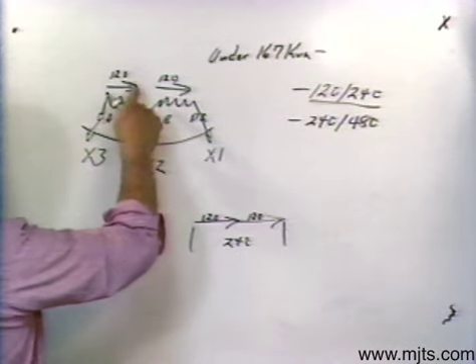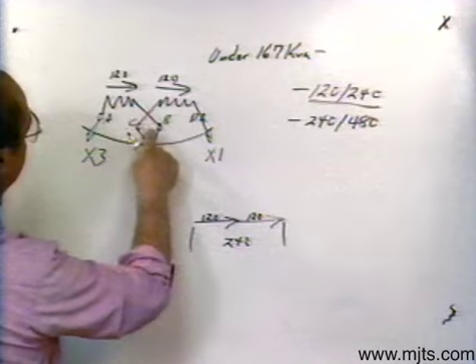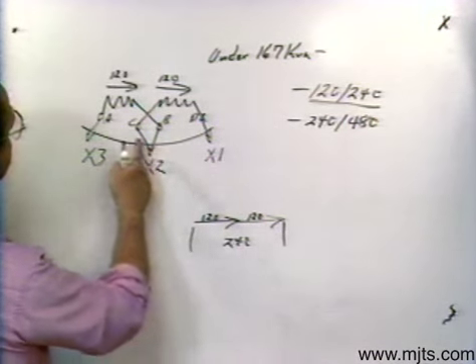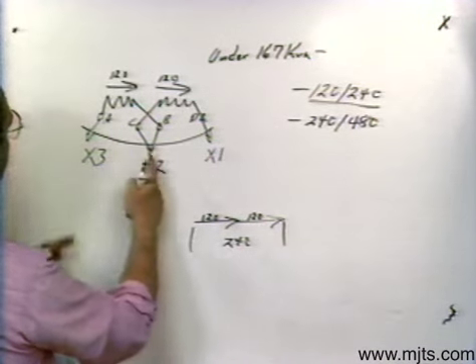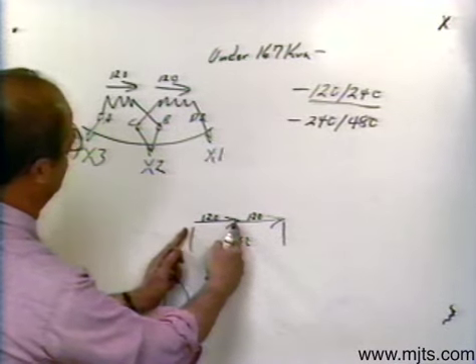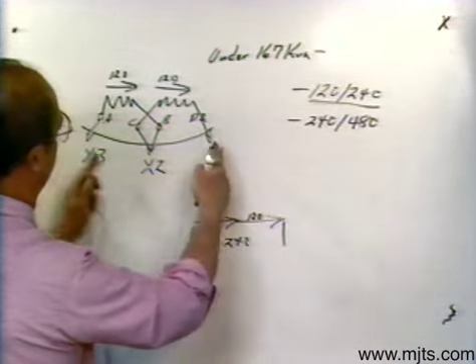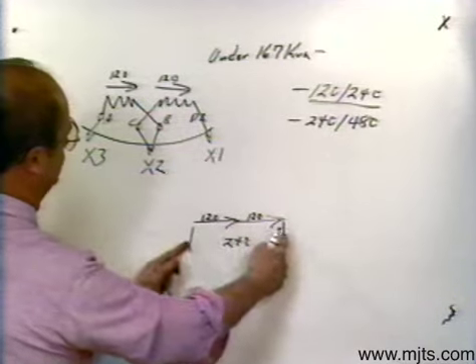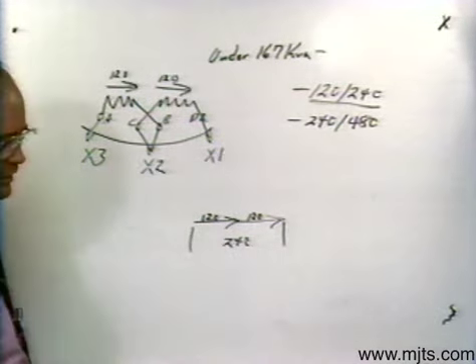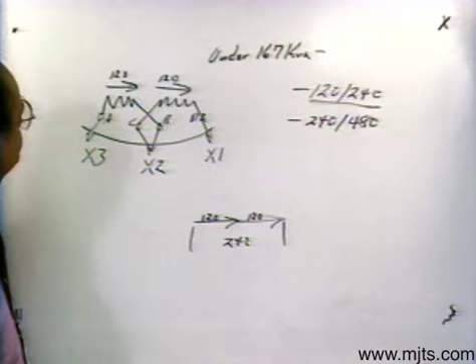If I series connect, I'm going to go head to tail and connect C and B to the center, so I would get half that value — 120 volts on one half, 120 volts on the other half, and 240 volts all the way across. We can graphically represent it exactly like that.